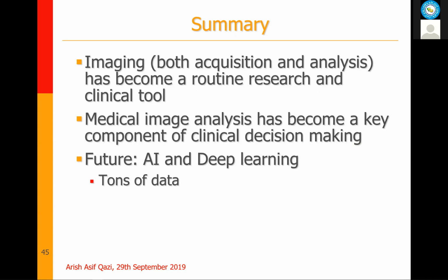Now, another problem is regulatory limitations. Any algorithm that you develop actually needs approval. You can't just develop a method and release it. It needs to be accepted by the FDA or European authorities. Now, the FDA has been very conservative about approving deep learning systems. And even if they do, they accept the systems in a locked state, which means that those systems cannot adapt themselves to new data. And if they have to retrain their methods on new data, they have to apply for another approval. Will these things change over time? Time will tell.